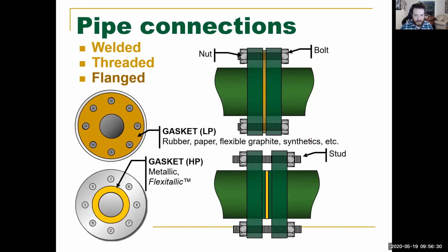Now, with these high pressure systems, instead of using a bolt, which is attached and has a head on the top of it, forged onto it, unfortunately what happens with those is the bolt head can fling off. But it is really difficult for nuts and threads to fail. All right. So on high pressure systems, you'll basically use a stud with two nuts on either side of it.